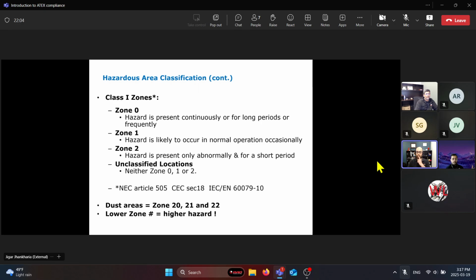So with North American standards making the move to zone classifications, would we need to recertify our existing Class 1 Division 2 certification on our battery products that we have today? No, they're independent. So the choice is yours. Do you want the zone marking? If you want the zone marking, as part of the ATEX certification, we can do IECEx. It's not going to cost you anything significant.